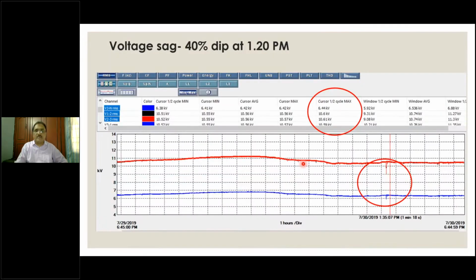In the same hospital case, if you remember, in the same 24-hour window we identified a sag occurring, a dip in voltage, as you can see here, highlighted. Here, the half cycle cursor I have kept shows the voltage available in one phase, as against 10.6 kV. It's an 11 kV supply, if you remember, HT side measurement. The voltage has dropped to 6.44 kV. That's a substantial drop in voltage, which can cause interruption to electronic equipment.